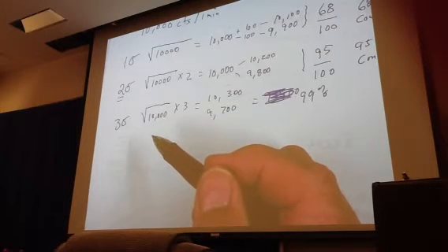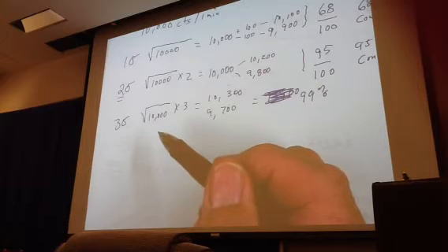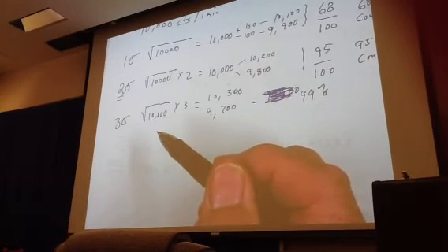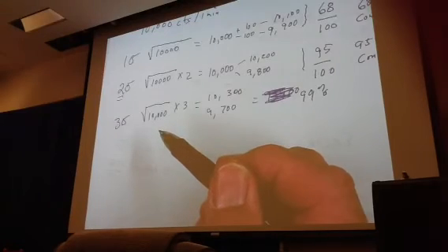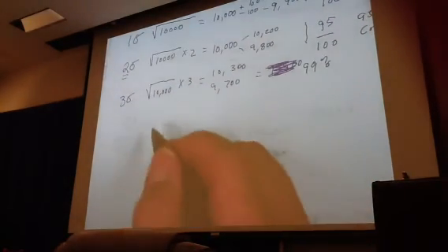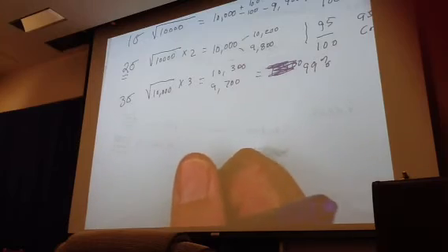Okay? And the number of counts that you collect depends upon the matrix that you use to accumulate your uniformity. So if you use a 64 by 64, all you need is about 4 to 5 million counts. And that puts 10,000 counts in each pixel. Because later on you're going to find that we have another formula that we use to calculate how many counts you need for a certain standard deviation.